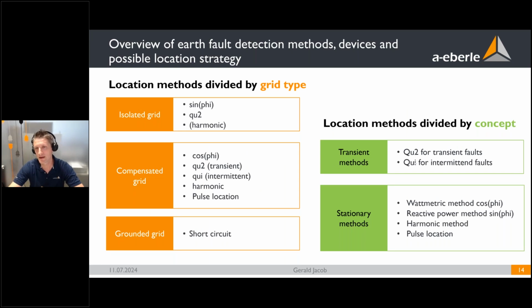There's also QUI for intermittent faults, which is also transient but repeating intermittent. On the other hand, for stationary faults, we have the wattmetric method, cosinus phi, the reactive power method, sinus phi, the harmonic method, and pulse location.